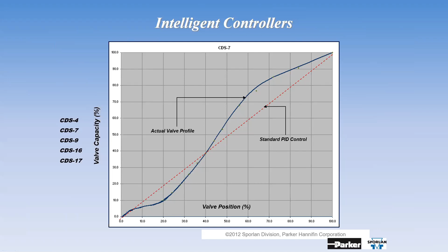Is it a produce case, etc.? We can delay opening on startup so that when we turn the store on, we don't blast the valves wide open. We gently ramp them up so that we're just not sending a boatload of load to the compressor rack. We can also tell them to be delayed after defrost. Why do we do that?